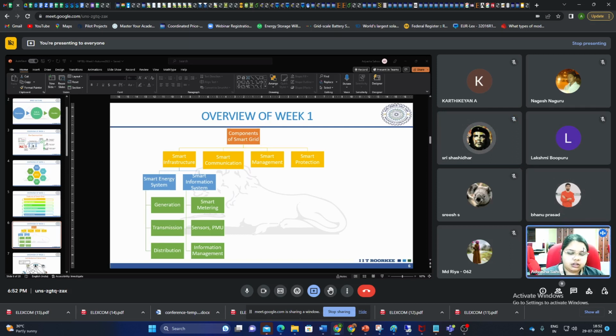Is it voltage or some other quantity? Since this is active power, and active power is not strongly related to voltage, it is some other quantity. Frequency, correct. Our active power is closely related to the frequency component. So any mismatch in active power will reflect in the frequency of the grid. And whenever there is a dip or rise in frequency, we have relays to protect our system, and that will lead to tripping of the system.